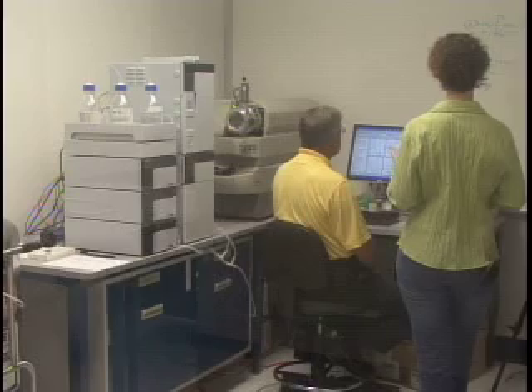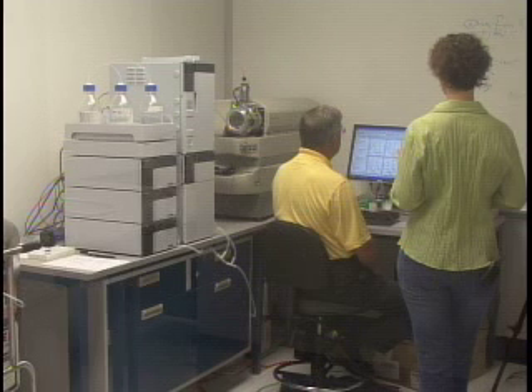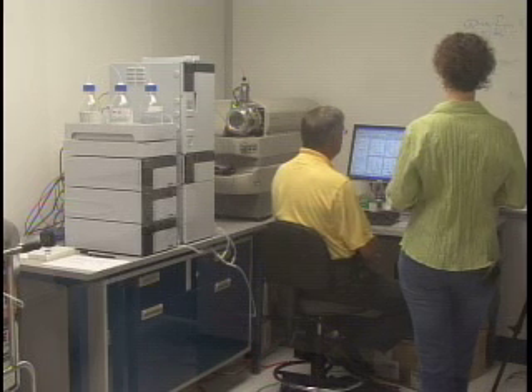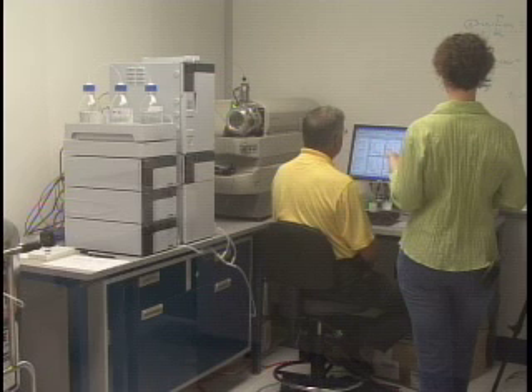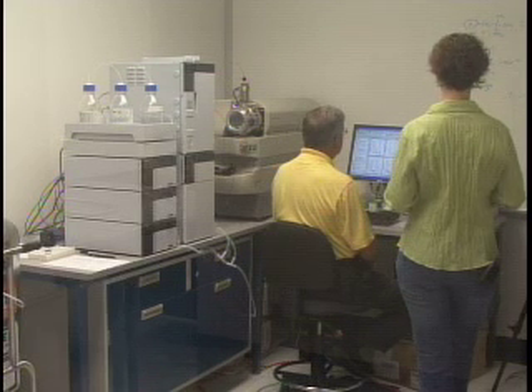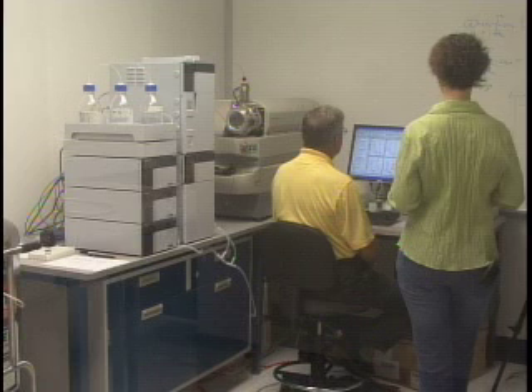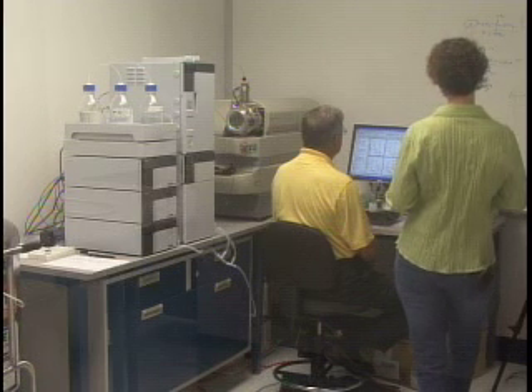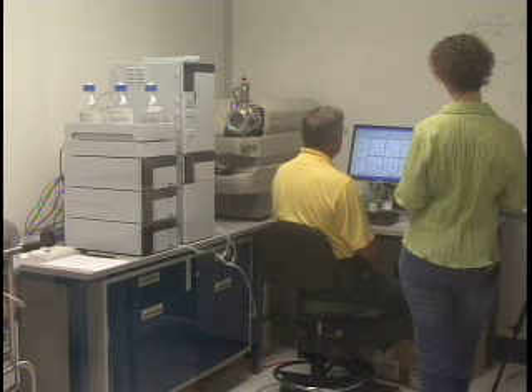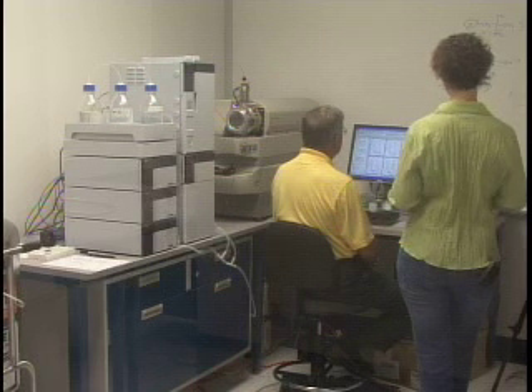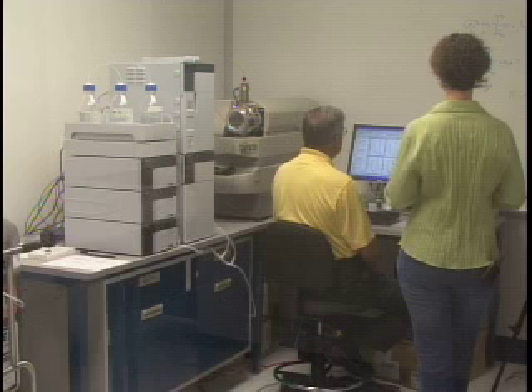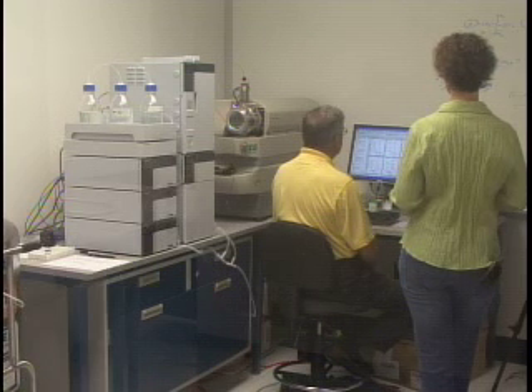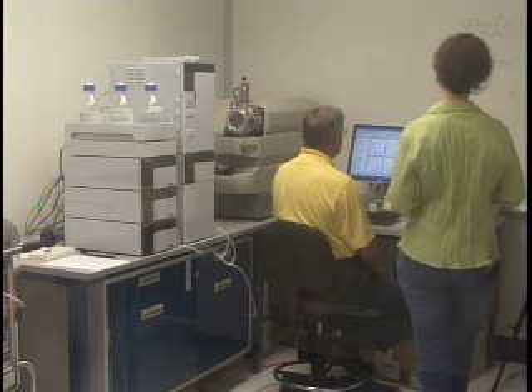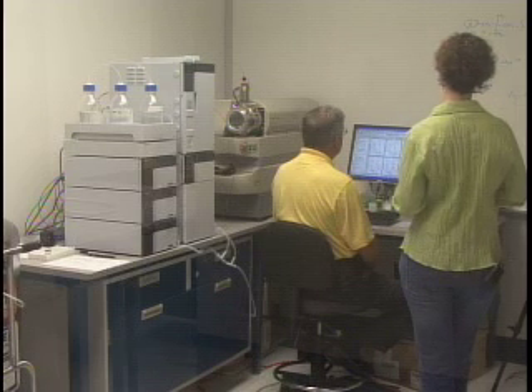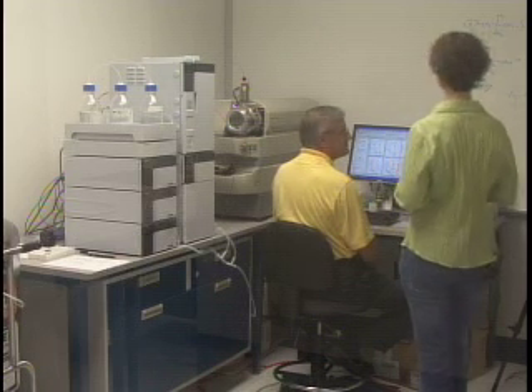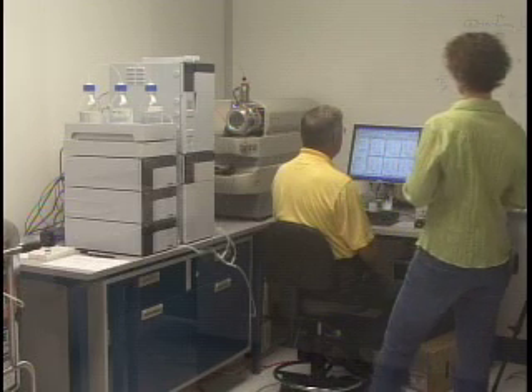And it's going to perform for Q1 and Q3 a series of what it calls iterations, where it evaluates the PPG tuning solution and then checks it against the parameters to determine if it's acceptable, and it alters the calibration table results accordingly. So while we're running this function, it's going to update the calibration tables in the software. Isn't that right? Yes. Okay. Don't want to misspeak. Don't want anybody to be confused.